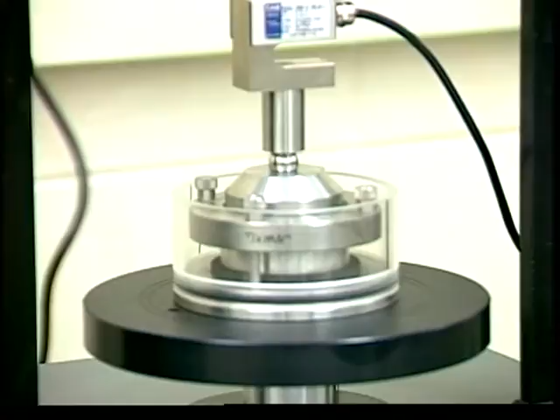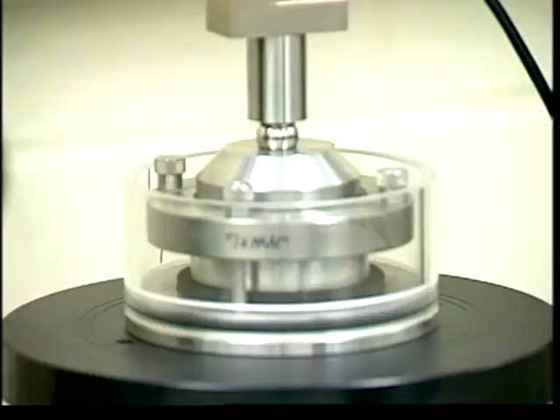So now my calibration is done for the load deformation. I have the characteristic curve for the machine calibration. I have about 0.03 inches of deformation of the machine when we apply 32 TSF, which translates to about 2,500 pounds, the weight of a small car.